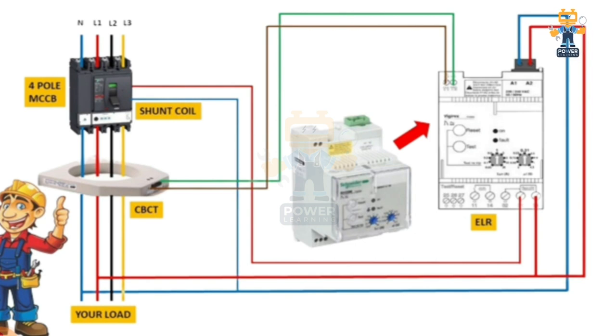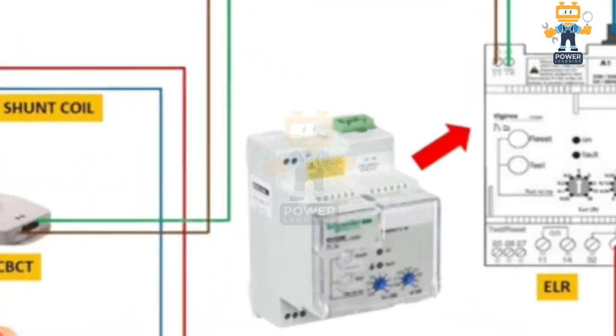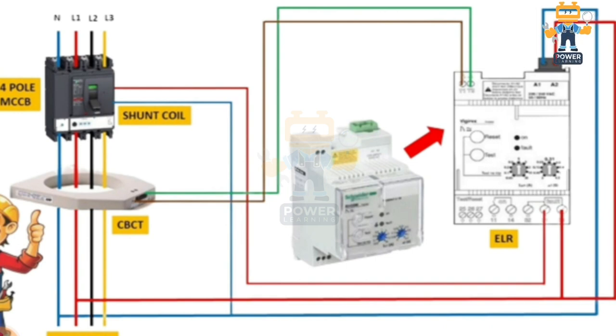Here you can see this brown and green wire — we are taking these from the CBCT and connecting them to our earth leakage relay at terminals T1 and T2. This is the simple connection of the CBCT with the earth leakage relay.